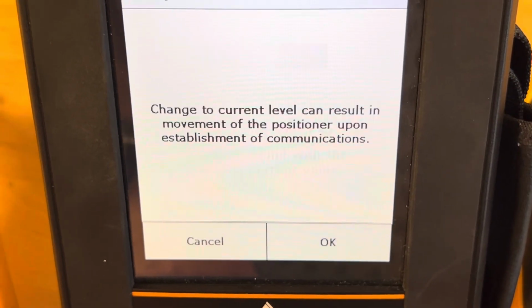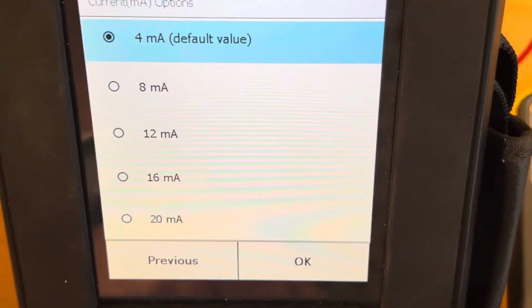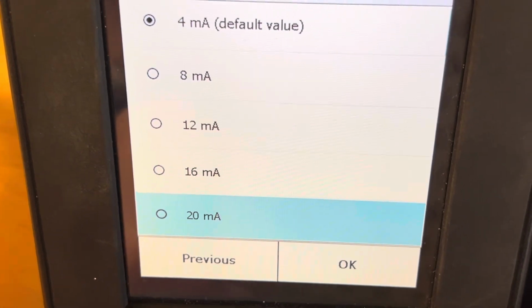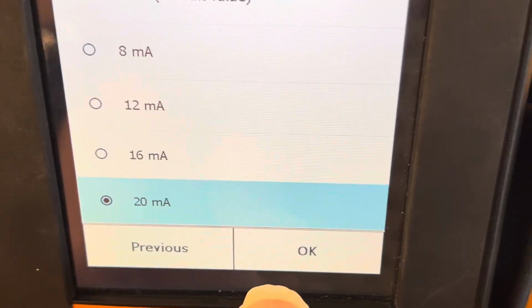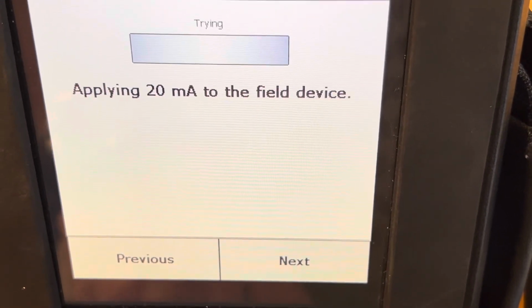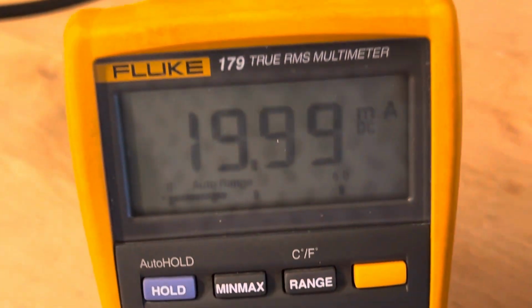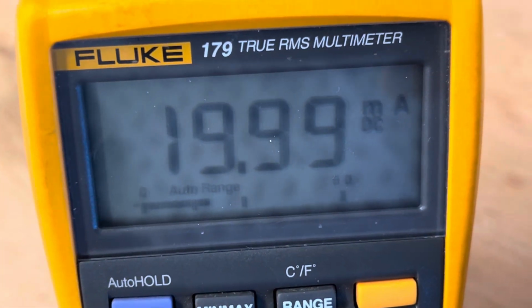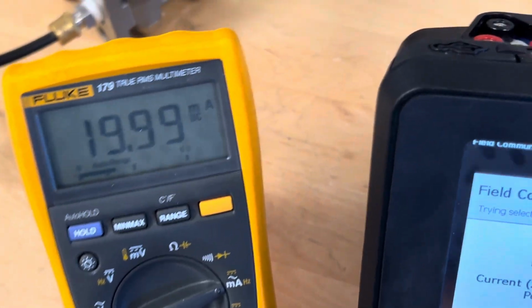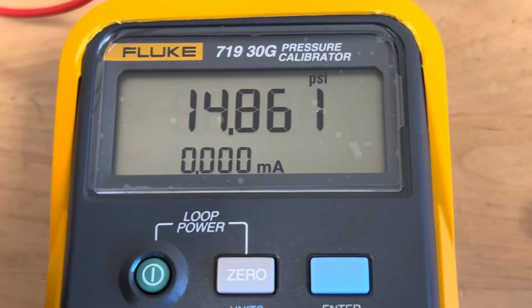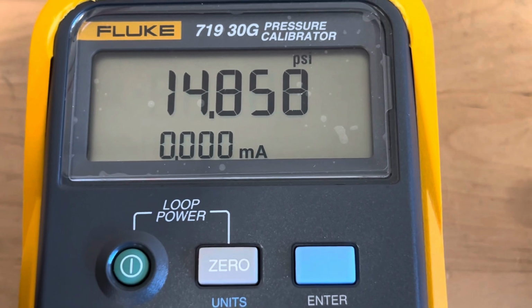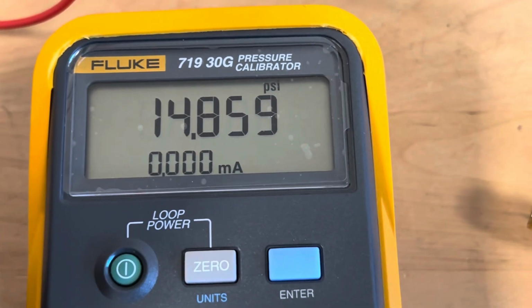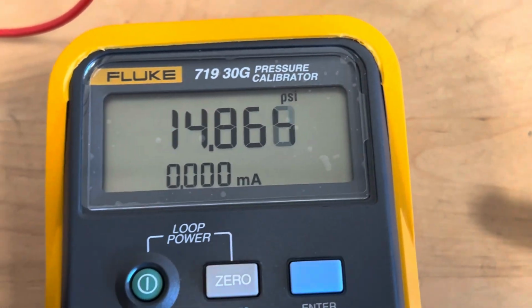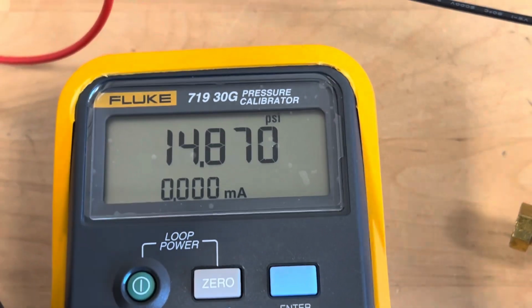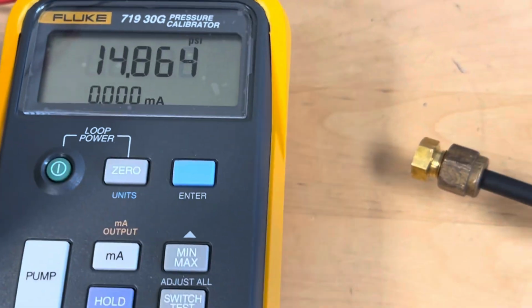So I'm going to hit previous. I'm going to hit OK. Now I'm going to give it the 20 milliamps. I hit OK. I see that I have 20 milliamps going to the unit. I check that with my Fluke. And if I look at my PSI, I'm at about 14.8. And I want to be at least 15.0 something something. I'm not too worried about the something something, but I want 15.0.